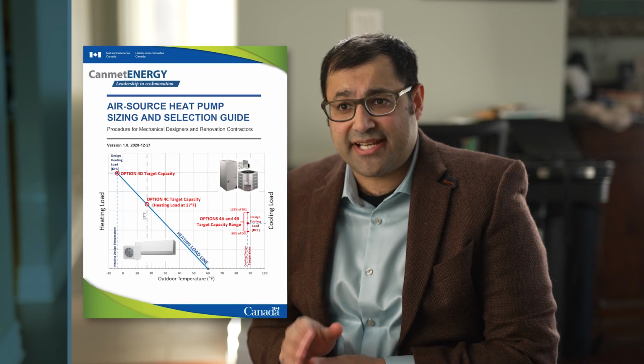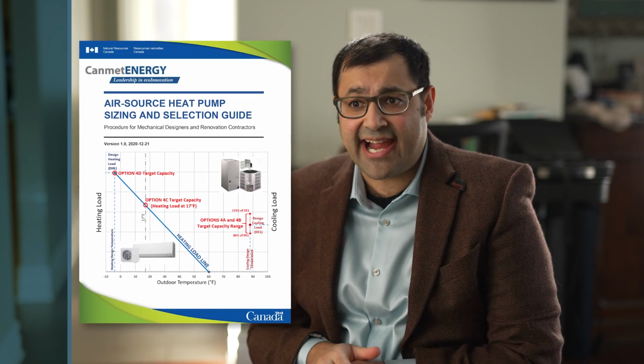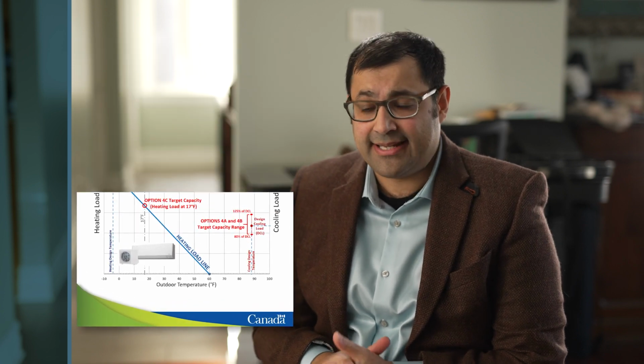We found that CanmetENERGY's air source heat pump sizing and selection tool was a good stepping point between the EnerGuide and the equipment selection. It's a useful way for contractors to see what the impacts are of the various heat pump models and communicate the optimal size to their customers. We're pleasantly surprised how well the smaller heat pumps keep up, even on the coldest days.